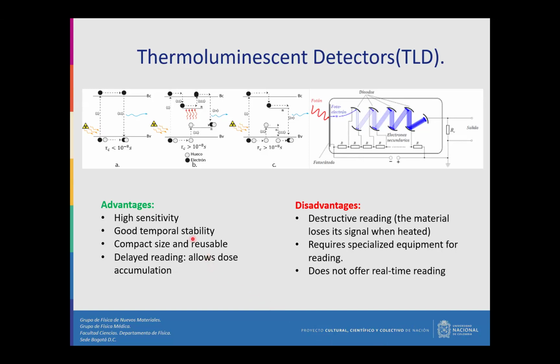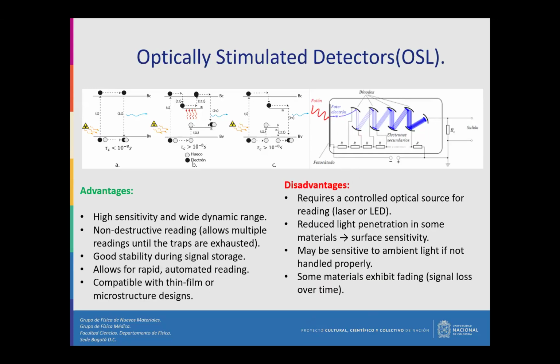They have high sensitivity, long-term stability, compact size, and are reusable, and delayed reading allows dose accumulation. A disadvantage is the destructive reading: when I take the information of the energy that my detector has, I can't take this information later. So I just have one opportunity to take that information, okay? And we have a big problem: it's not suited to real-time reading, because I need big equipment like a photomultiplier to take the signal, okay?